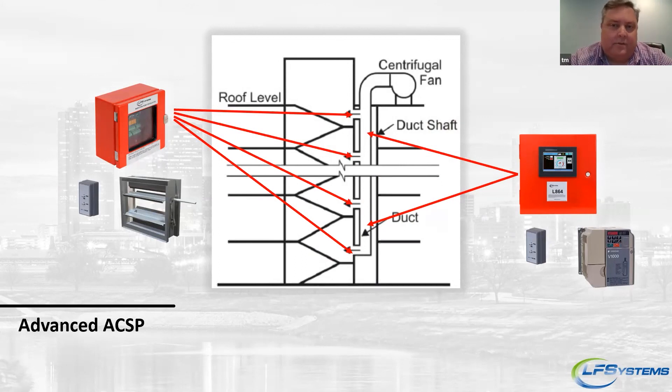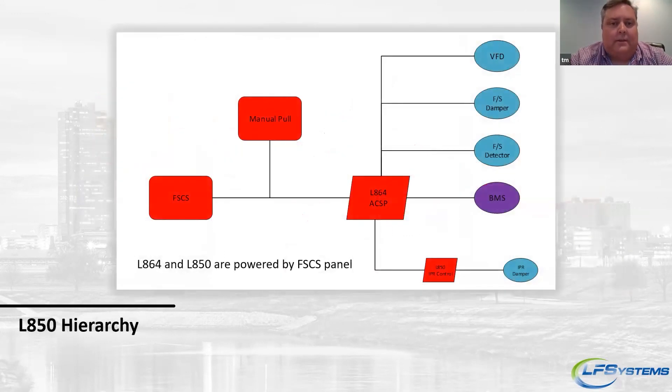This shows how the system goes together. You have your main L864 controller and then subcontrollers with the L-850 for complicated systems. Typically, just the main L864 controller is needed. Per NFPA 92, the controller needs to be activated by a manual pull or the FSCS, which we can accept. We then drive the system, perform all checks — fans, fire smoke dampers, fire smoke detectors — and send information out to BMS so it can monitor system status. The L-850, when present, operates as a sub to the L864.